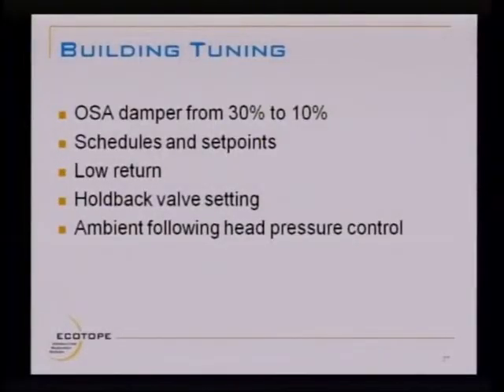The schedules and set points were such that, again, this is something that can be pretty tricky. The heating set point was set back at night, which is a good idea, not to use so much heat at nighttime when the customers aren't there. But the set point for the heat recovery was also set back, so that in the morning, when they wanted to heat the store back up to operating temperatures, the gas heat would come on every time because the store just couldn't heat up fast enough on the heat recovery alone. So we went back and we just said, well, there's no reason to set back the heating set point if you're using heat recovery, because you want all that energy in the store. So just leave the heating set point for the heat recovery high all the time.